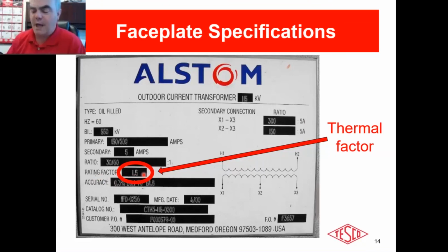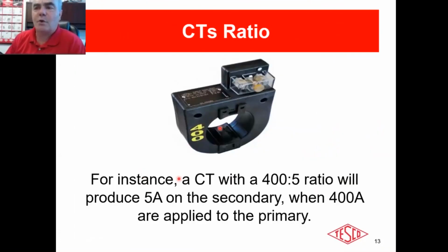What's the problem in that? Well, what is a transformer? I basically got a whole bunch of turns in here, okay? In this case, I got 80 of them. We know that. I got one primary that's going to be coming through here. Well, I got 80 turns, and what are they encased in? They're encased in traditionally some sort of butyl rubber, or some sort of hard encasement, that holds those windings, all right? As long as I don't catastrophically fail the transformer, that transformer is going to be just as accurate in 30 years as it is today.